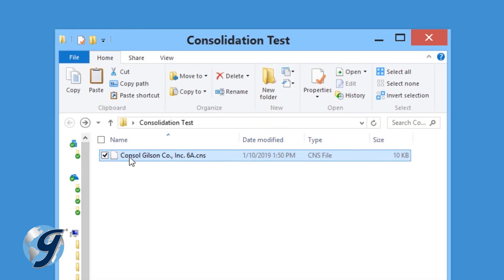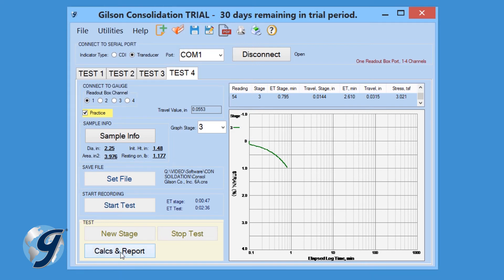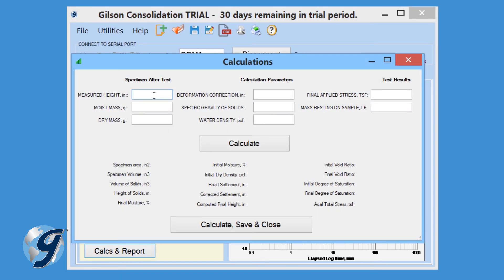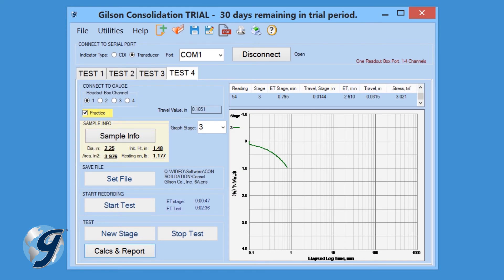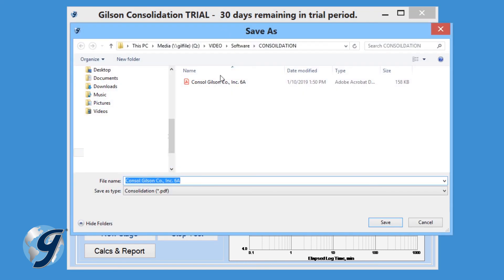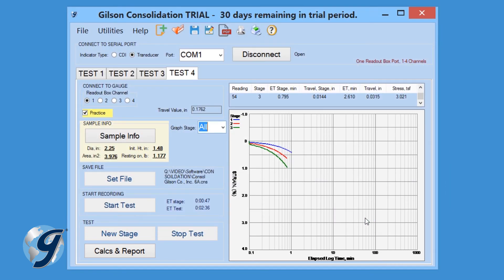Now that you have the final values, reopen the test and select the Calcs and Reports button. Enter the specimen after-test values and the calculation parameters, then click Calculate. The calculated values will appear in the bottom half of the menu. Click Calculate, Save and Close to save the calculations and close the menu. Now the data collected will automatically be ready for analysis or export. You can preview, print, or export your data for each stage of the test or for all stages of the test.